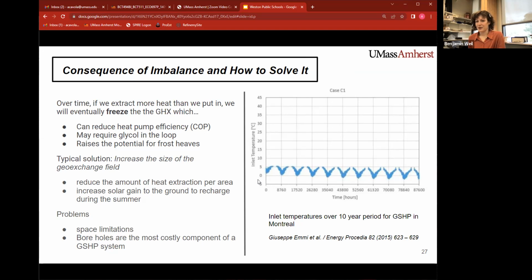A typical solution would be to increase the size of the geoexchange field. This works because it reduces the amount of heat extraction per unit of area and increases the amount of total solar gain to recharge the system during the summer. The problem with this is space limitations and also cost limitations. The boreholes are usually the most costly component of a ground source heat pump system.